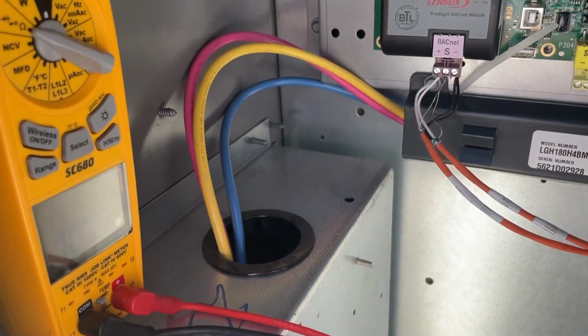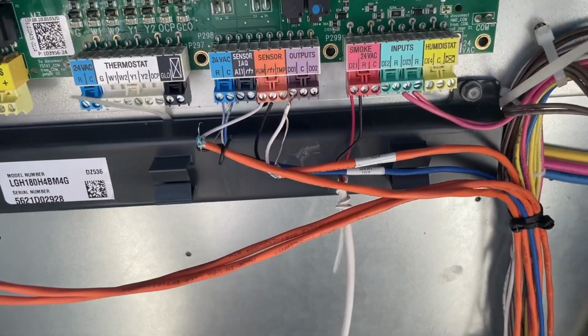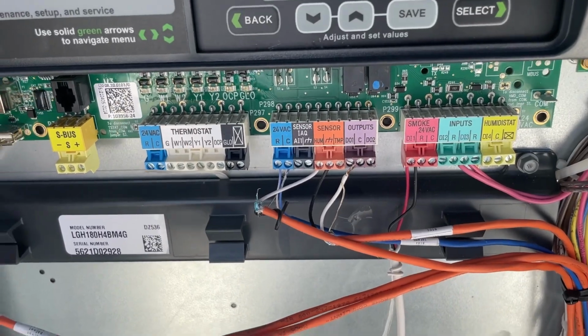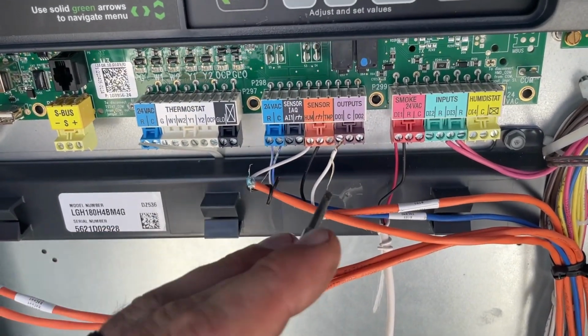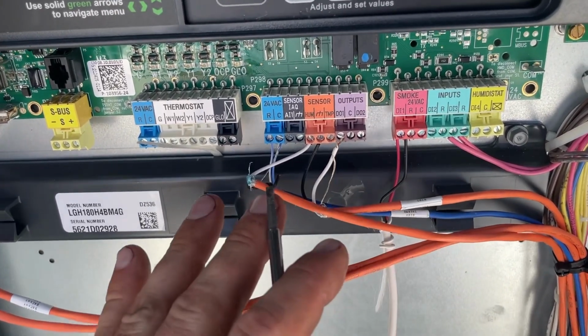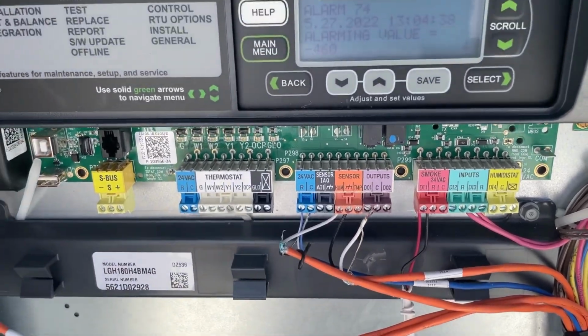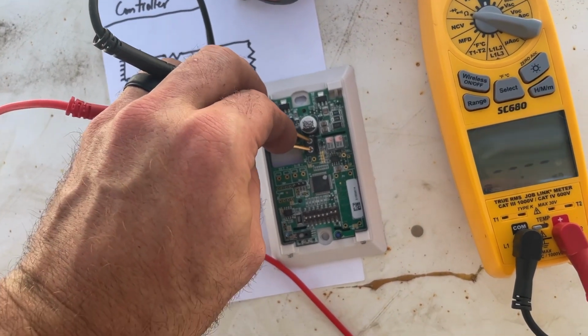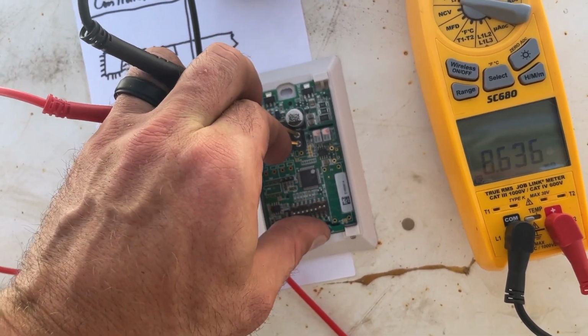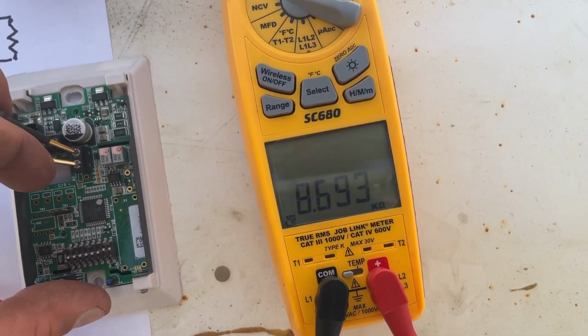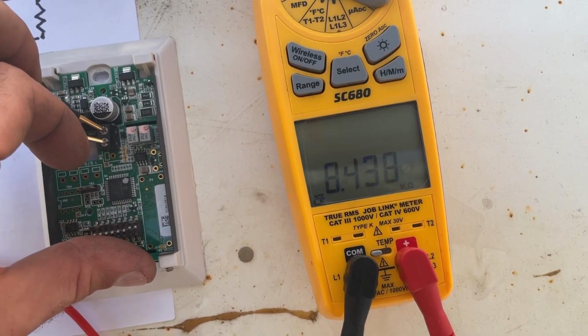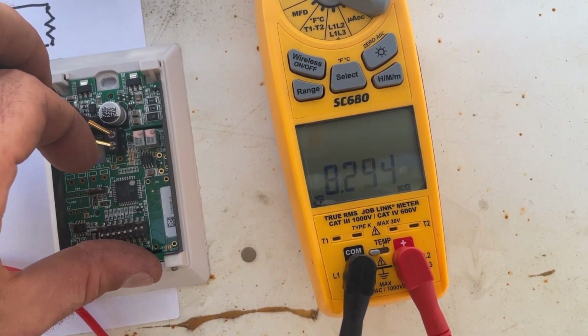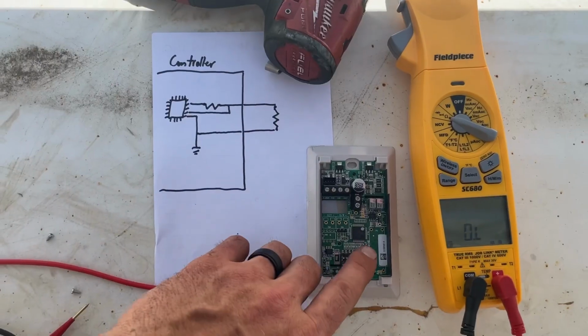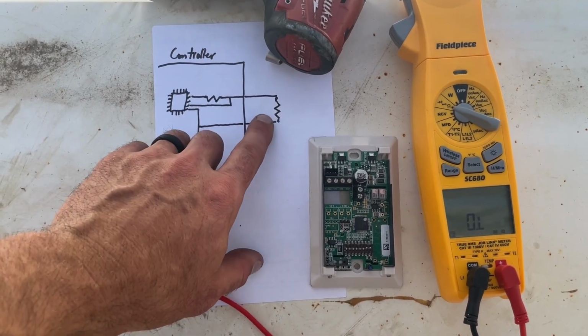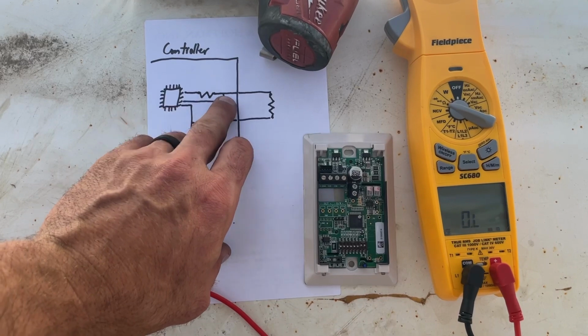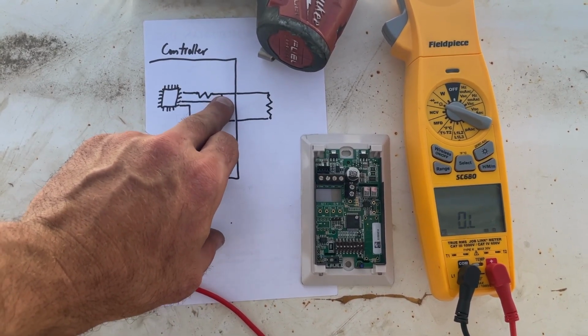And that's what I did. We're going to go down and look at this zone sensor, and I may or may not be able to talk. It just depends on who's got their eyeballs on me. But what you're going to see is I disconnected the wires from the thermistor on the circuit board and just put in my own 10K thermistor, and that's how I got them going. Here's the zone sensor, and I'm on this connector, which is connected to this thermistor. So you see my reading there? Now watch as I warm this up. See it going down? And that's exactly what you would expect. This thermistor here had gone open circuit. So what the chip was reading right here at this point was 3.3 volts, and that's how it knew that there was a problem with the thermistor.